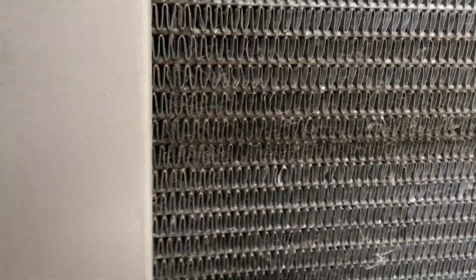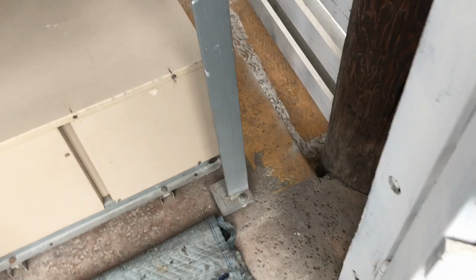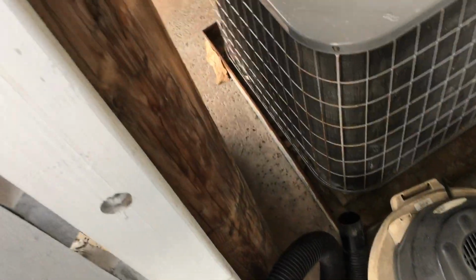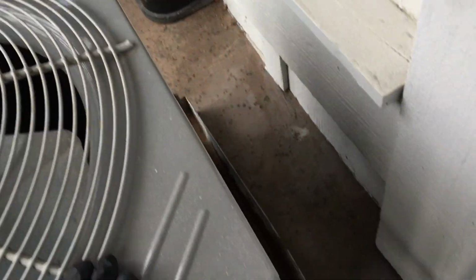For sure we need a hot water wash on that. Okay, man, that place is dirty. All those, all cleaned up in there. Vacuum condensers. Tons of debris. Man, the amount of debris around here was just freaking insane. The place was dirty. I cleaned it all up.